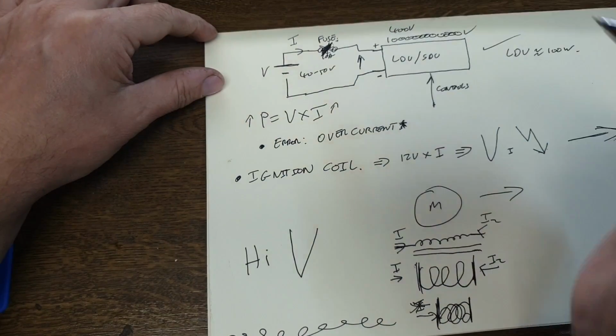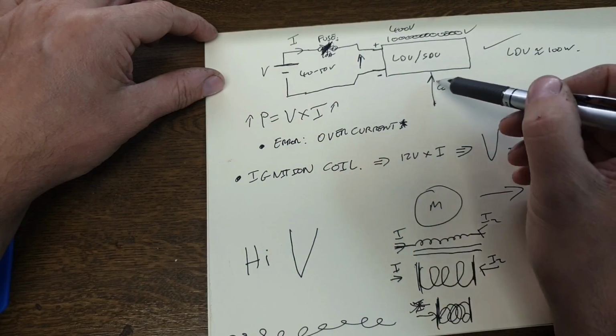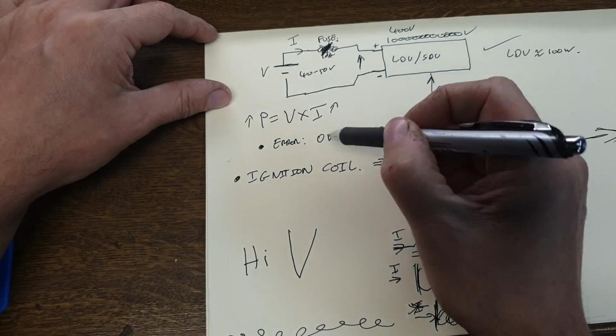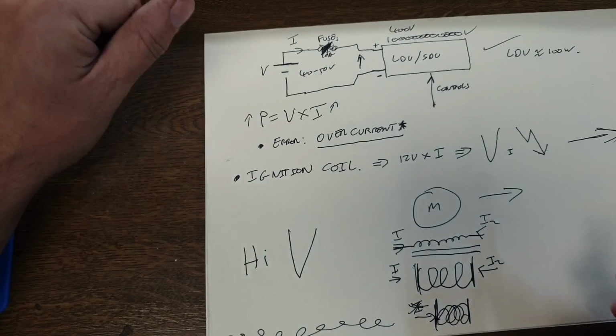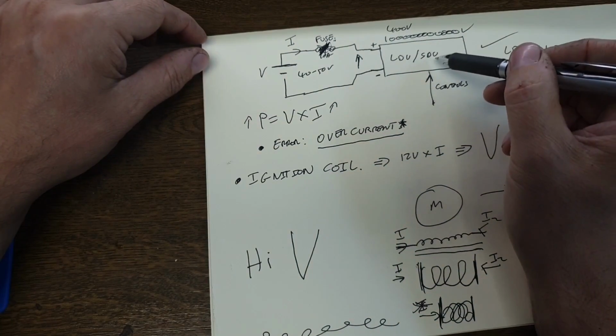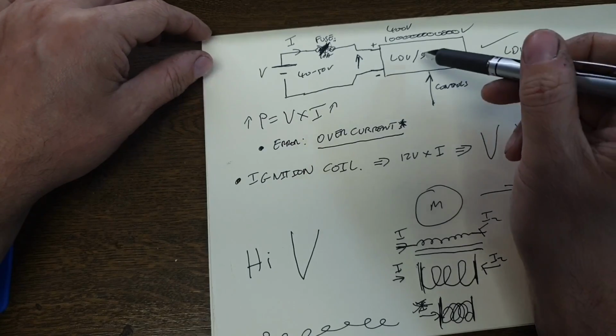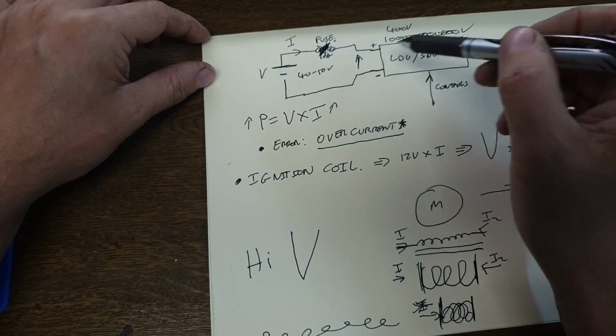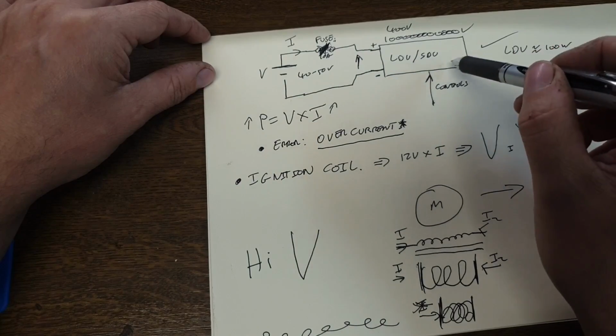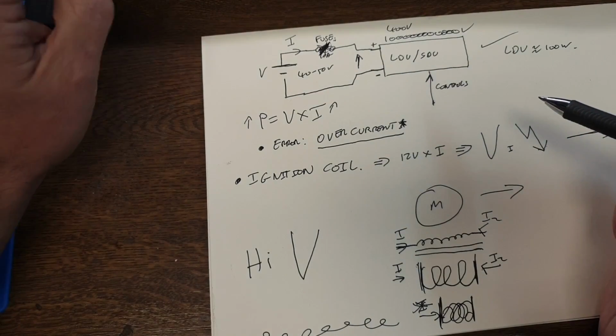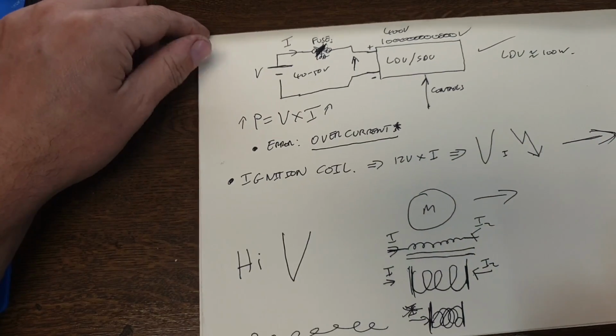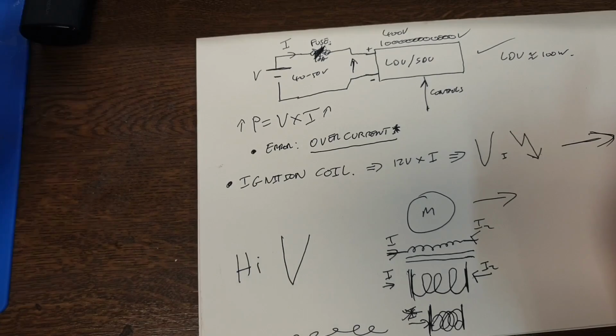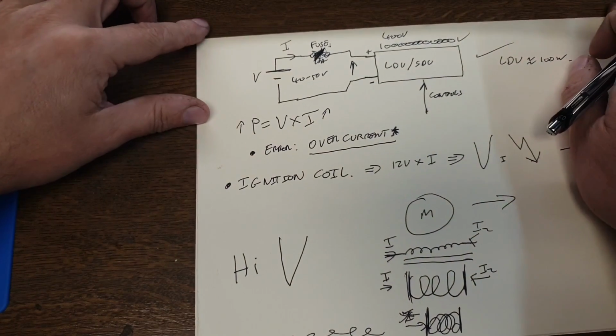So when you replace the fuse and come back and attempt with your control signals to restart, you get overcurrent, because the logic in here can no longer control the necessary transistors to send voltage and current into the motor part to make it spin. The inverter is damaged—not necessarily beyond repair, but given the design of some of these things, probably beyond what the repair of most people, myself included, can actually achieve.